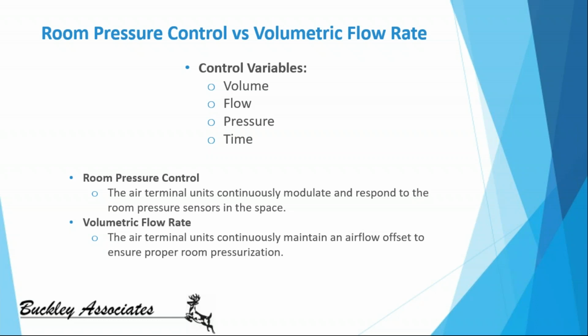Let's say somebody opens a door leading into the space. What is immediately going to change in this space? The pressure of the space. So if we were operating based on pressure, a signal is going to be sent to an air control valve. We're going to wait a certain amount of time for the pressure to either build up or drop down to meet a certain pressure set point. So what did that take? Time. So this variable is dependent on many things.